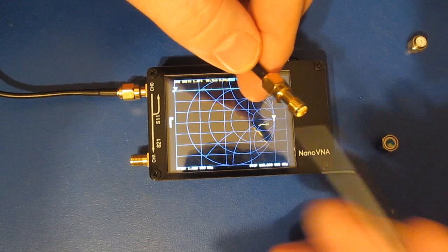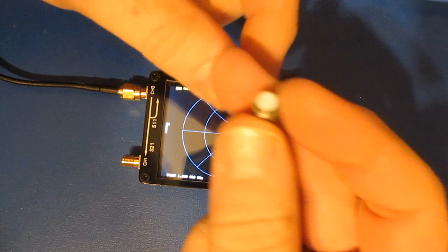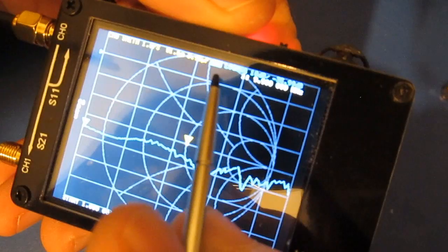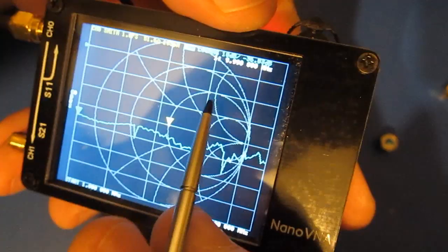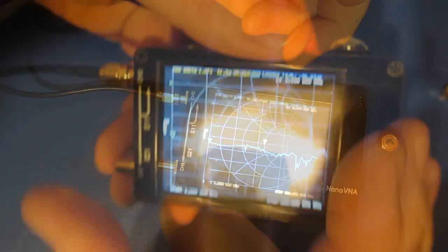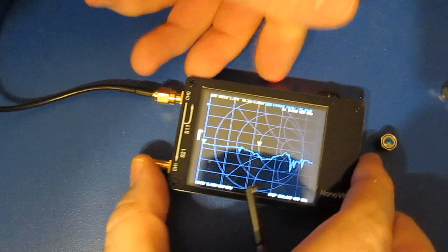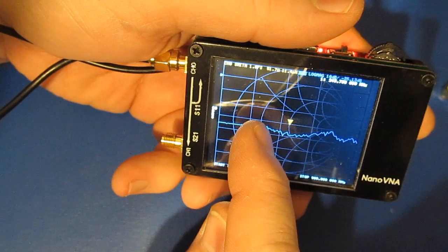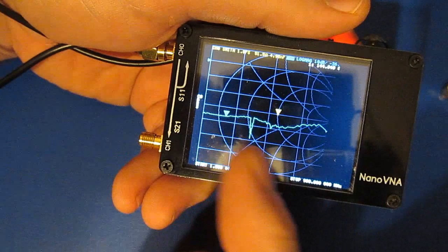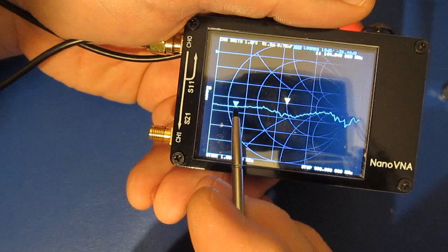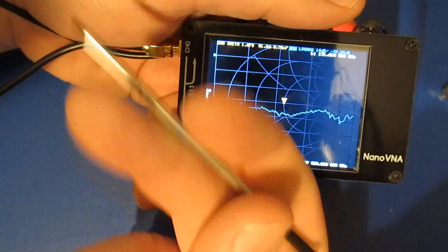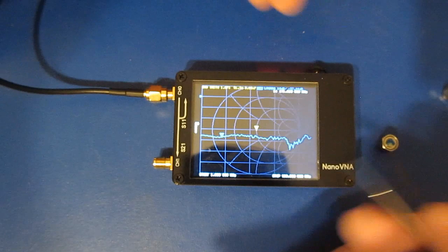This happens to be a resistor from Midwest Microwave — this terminator is rated for DC up to 18 gigahertz. We can see it's showing log mag, 10 dB per division. The cursor is at roughly minus 36.02 dB at 1 megahertz. I can grab this cursor with my finger, though the stylus works much better. You can see I'm dragging the cursor across. I'd rather not use the stylus at all — you can actually run this unit with a PC via the USB port. Let me plug it in and show you what their software looks like.